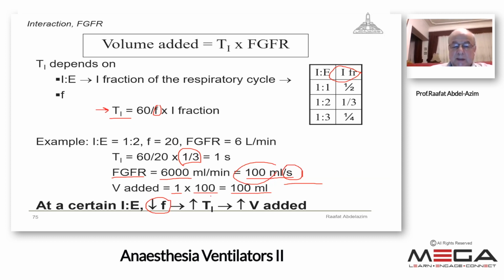In 2 seconds, we multiply 2 times 100 ml if the fresh gas flow is 6 liters per minute, so the added volume will be 200. So whenever we decrease the frequency, this will lead to an increase in the inspiratory time and an increase in the volume added. To summarize, the volume added depends on the fresh gas flow and the inspiratory time. More fresh gas flow, more addition; more inspiratory time, more addition.